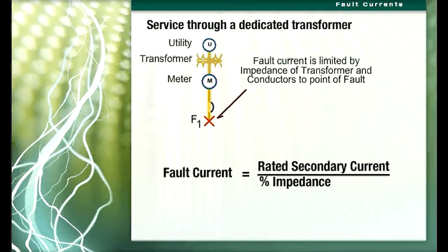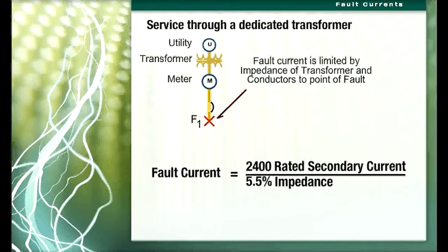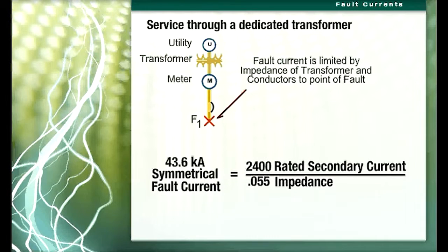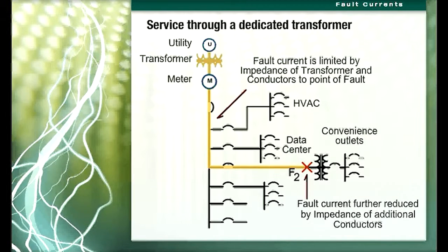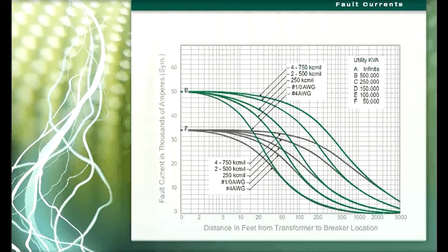For a 2000 KVA, 5.5% impedance transformer, rated current is approximately 2400 amps. The fault current at the transformer terminals would therefore be 2400 divided by 0.055, equals 43.6 kilo amps symmetrical. The fault current available at F2 is further reduced by the impedance of the additional conductors. The plot shown here illustrates the limiting effects of transformer and conductor impedance.